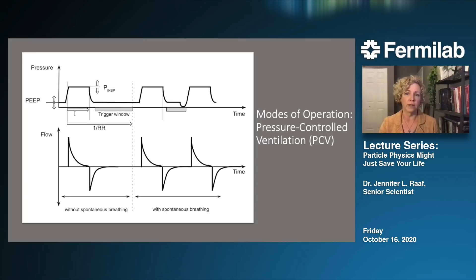So when the control software sees an acceleration of pressure change going in the negative direction during the trigger window, which is set to be during the exhalation period, then it will synchronize with the patient's desire and immediately initiate another inhale. So in PCV mode, a new breath can be initiated either after a full breathing cycle has completed, or if the patient starts to spontaneously inhale during the exhalation window.